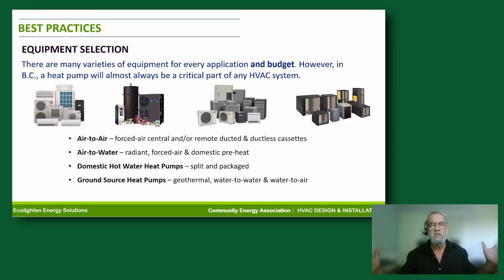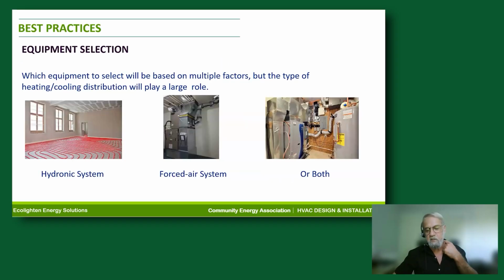There's a lot of product out there. So what to choose? Well, one of the first things that'll impact that decision, which equipment to use, is going to be how you're delivering the heat or the cooling to the building. If it's a hydronic system, that's going to be one thing. If it's a forced air system, it's going to be a different thing, or both. And both is not uncommon in the Vancouver area, the Lower Mainland. Whistler, for example, very common, where you've got an air-to-water system doing both radiant heat and forced air cooling, and some domestic hot water, among other things.